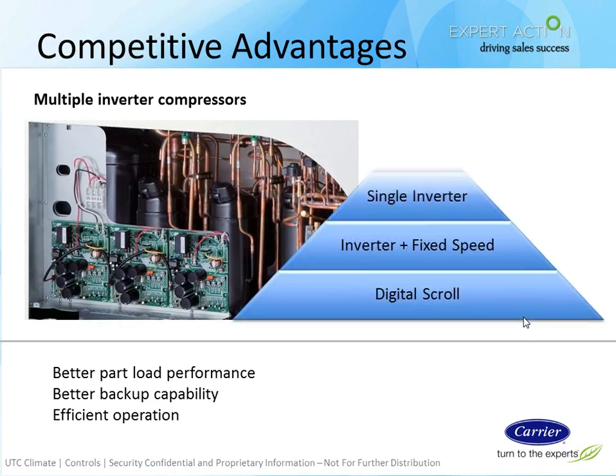Competitive advantages of the Toshiba Carrier VRF. We have multiple inverter compressors. Some of our competitors have a digital scroll or an inverter plus a fixed speed or just a single inverter. All our units have 3 inverter compressors, and they're programmed to run in their most efficient mode. So in that, the sweet spot for these compressors is about 80% full capacity.